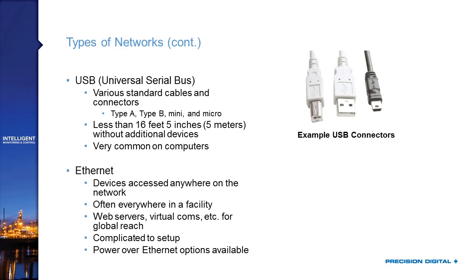Growing in popularity is Modbus TCP, essentially Modbus over Ethernet. Devices can be accessed anywhere on the network — realistically anywhere in a facility or even anywhere in the world if done properly. There are web servers and virtual COM port devices that allow connection wherever needed. However, all of that is fairly complicated. You need a solid understanding of your network topology to make sure all devices can communicate across all the hubs and jumps. Ethernet also offers the advantage of Power over Ethernet in facilities wired for it.